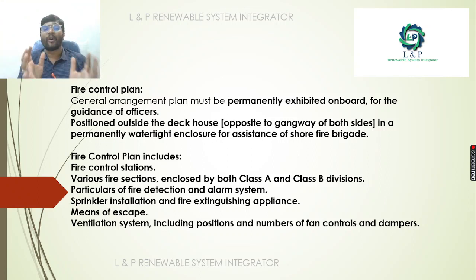Next, if you are going for a fire control plan, it must be permanently exhibited on board, and guidance for officials is very important. Also, a fire control plan can include the fire alarm control station and various fire sections, which can be classed into class A and class B categories, particularly the fire detection and alarm systems, sprinkler installation and fire extinguishing appliances, and means of escape, that is the ventilation system, including the position and number of fan controls and dampers.